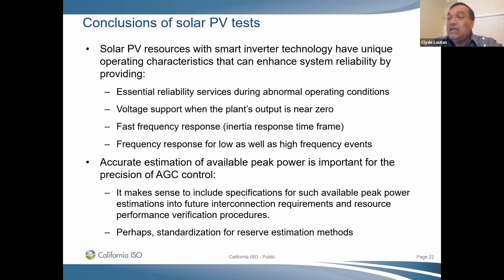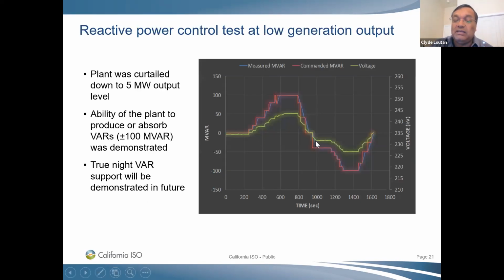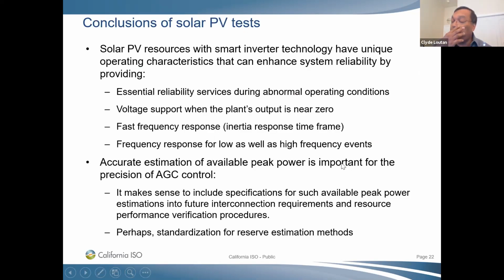So if your voltage is high, the inverters can operate in a manner to help reduce the voltage. On this plot right here, you can see we were able to lower the voltage to roughly 225. The actual operating range here is roughly 230, but we were able to consume reactive power on this plant, which is this area right here, roughly 100 megavars. The plant was able to consume to lower the voltage. So yes, the PV plants can both provide reactive power and also consume it.